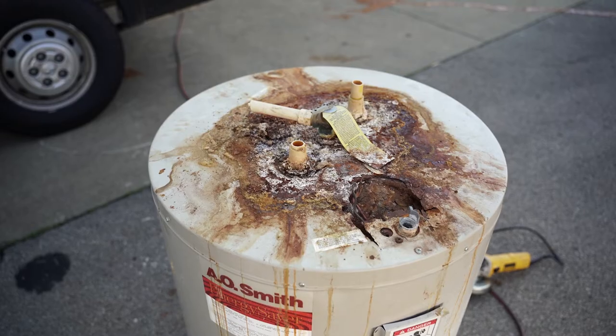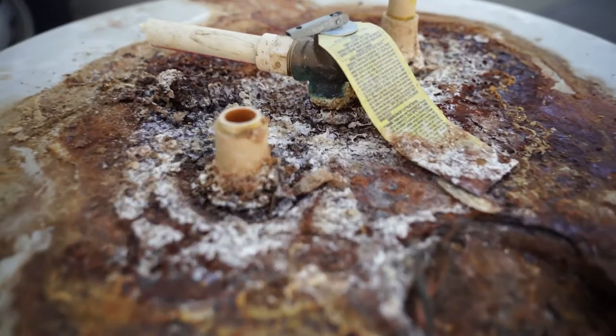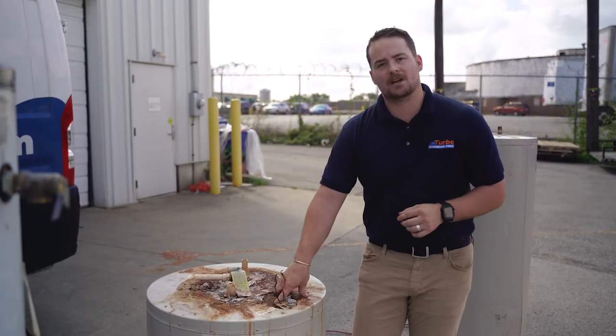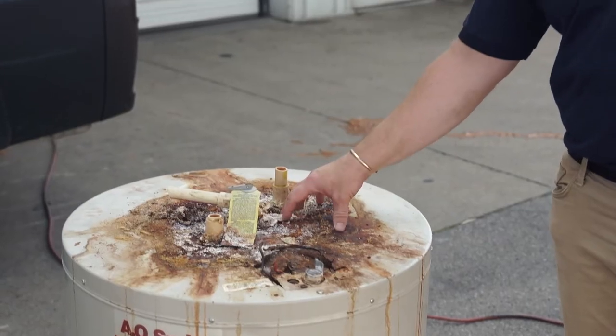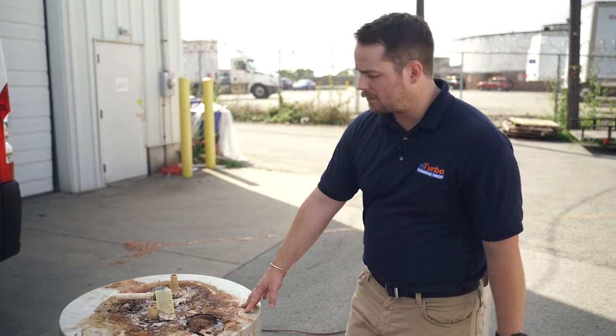As we come down here, we've also got another water heater from the early 90s, and as we can see, these warning signs have been ignored. We've got great buildup here — I can actually stick my finger through this protective shell and feel that membrane inside the water heater. We've got some real bad buildup here, and it can cause some leaks. It's going to weaken the metal jacket in the water heater itself.